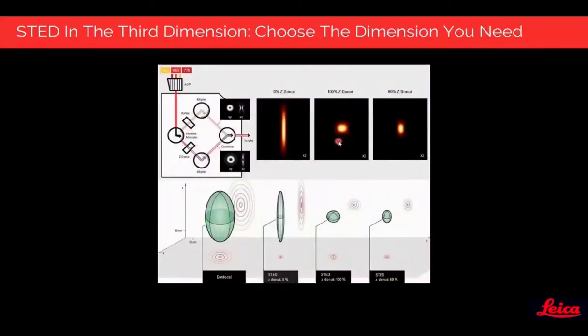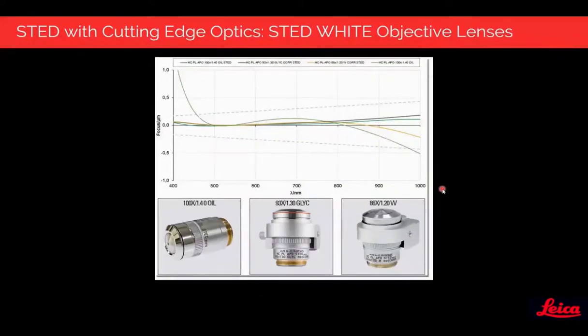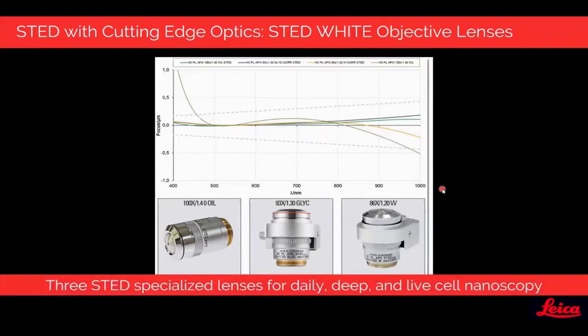We complement the white light laser and AOBS beam path with three STED lines covering the entire spectrum to optimize performance of suitable fluorophores. We can do 3D STED, selecting the dimension we need with our proven technology — allocating light to two STED pathways to get the best lateral or axial resolution, or tuning between them to optimize for the smallest focal volume. For 3D STED, we take care of inhomogeneities such as cover glass thickness, temperature changes, and refractive index mismatch using the STED White class of objective lenses with best-in-class optics, and we have three STED specialized lenses for daily, deep, and live cell nanoscopy.